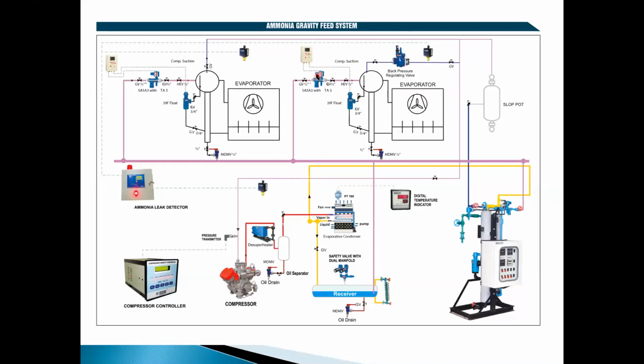This function is similar to the float switch we use in the water tanks in our homes. When the water level drops down, the float goes down and the cock opens. When the water level comes up, the float ball goes up and closes the cock. A similar function is achieved here using an electronic level controller and solenoid valve.